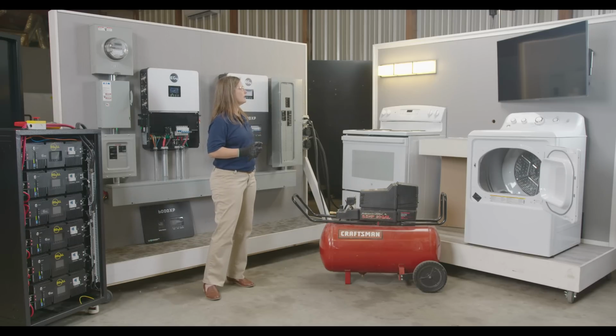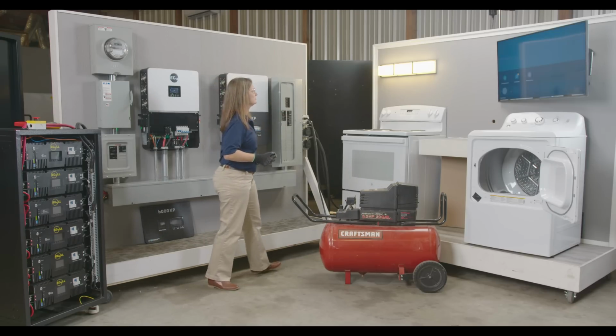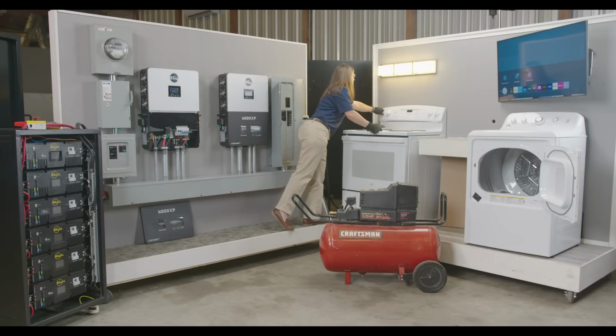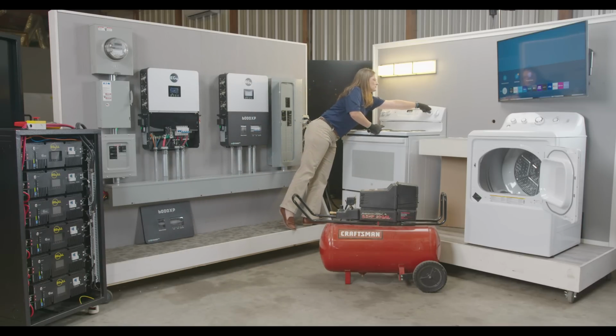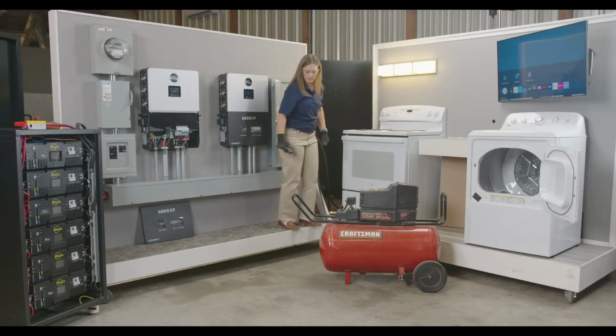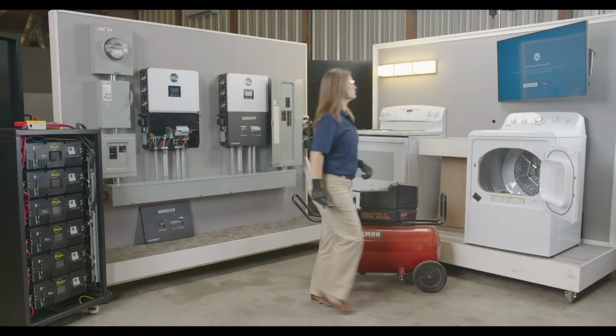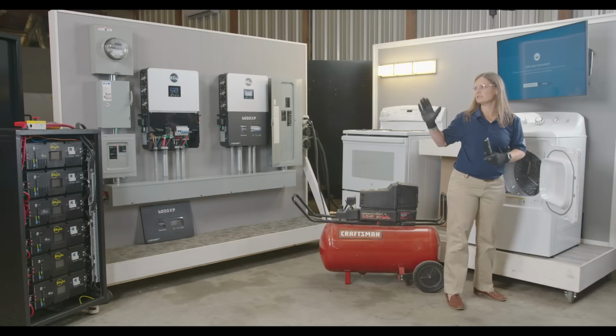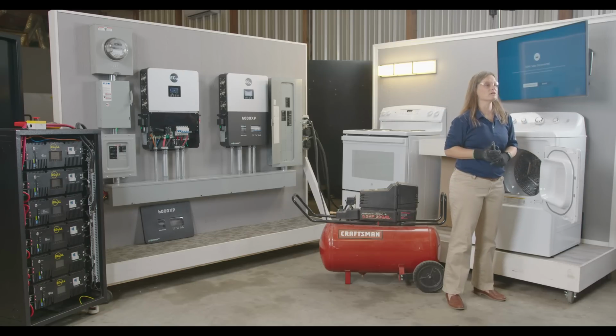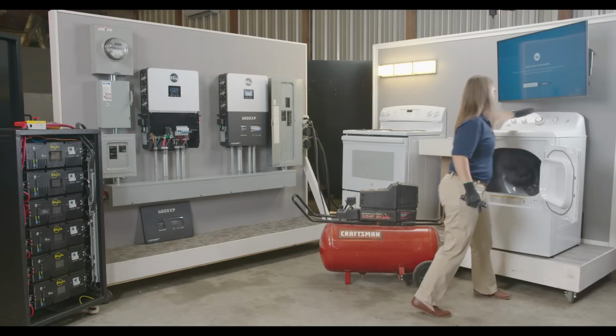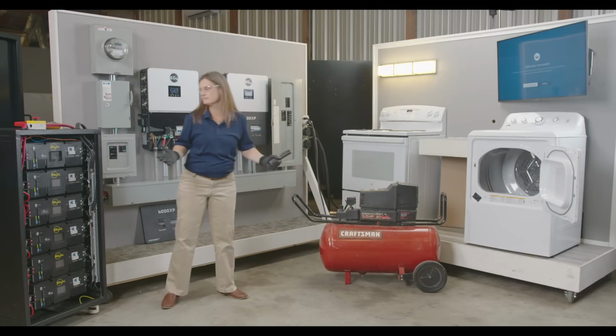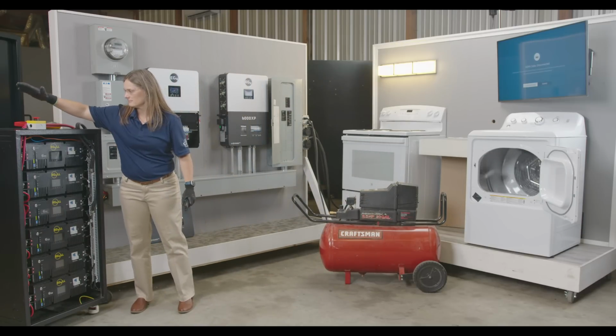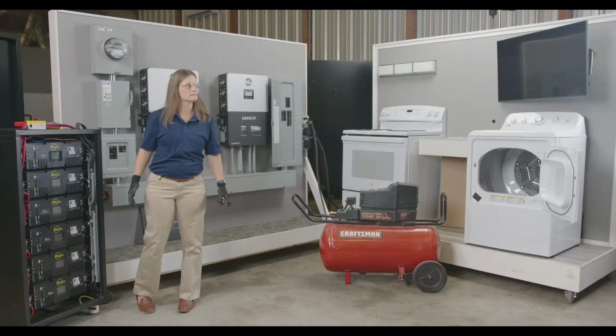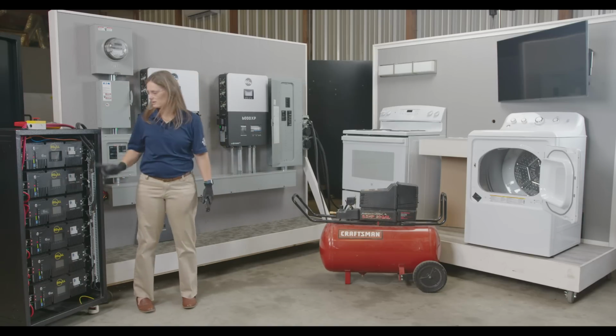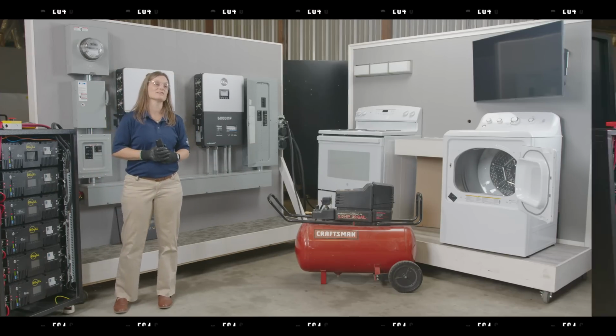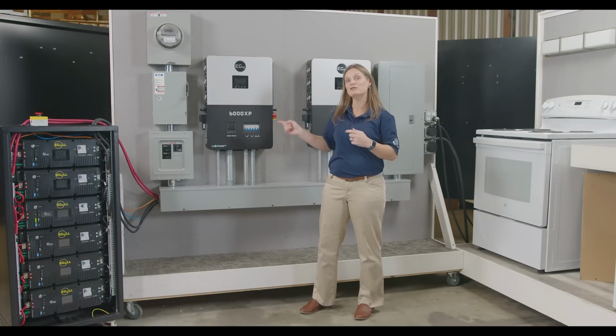So we've got our light on. We're going to turn our TV on. Flip on our burners. We're still running in parallel. We're able to power all of these loads. Let's turn on our dryer, and then we'll hit the rapid shutdown switch and see if everything turns off, including the breakers on our battery rack. Right, we're running, and lights are off, dryer's off, all of our breakers flipped. Rapid shutdown works.